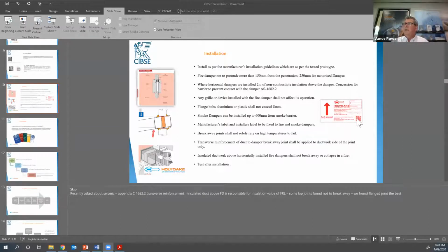That's an installer's label, and they're provided so that it can be fixed either to the ductwork or to the wall penetration next to the damper, so that each damper is uniquely identified. Now, that's actually a requirement, that each damper is uniquely identified within the building as well. So you've got a number of ways of doing it. You should be able to see it through the damper list, and that'll come with all of the data within the building. You should see the installer's label either on the wall or on the duct next to either the fire damper, smoke damper, or combined fire smoke damper.